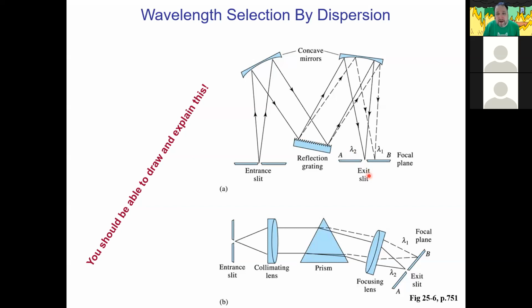Nobody would ever do it that way, because moving that slit is a tricky thing to do. So what they do instead is you take this grating and you rotate it. And there's a little stepper motor that's going to turn it a certain amount, and you can correlate by degrees of rotation which wavelength of light gets through. Okay, so you're going to turn that grating, and you're going to make that rainbow move lefty-righty, and only one wavelength of light gets through at a time.